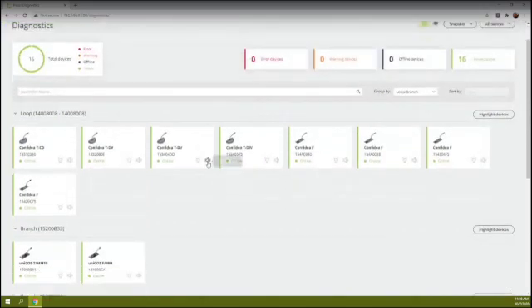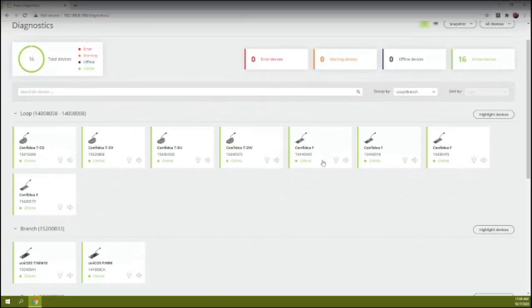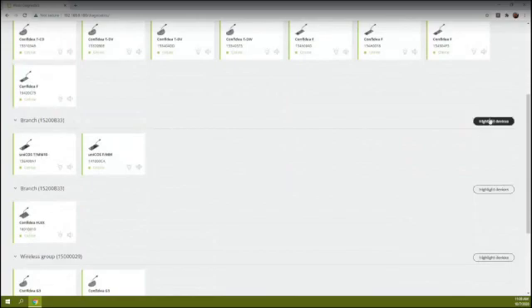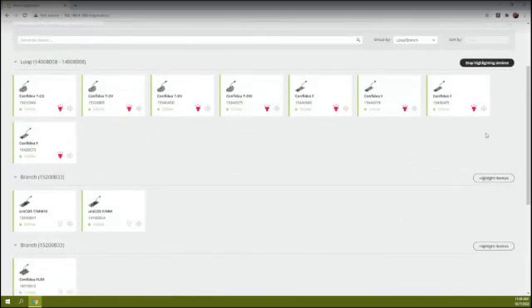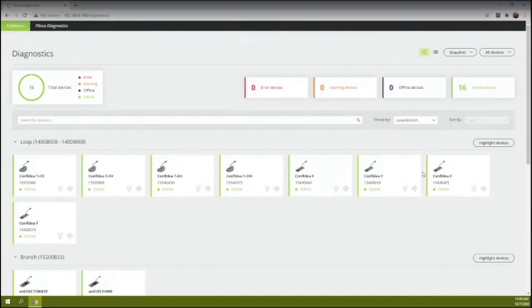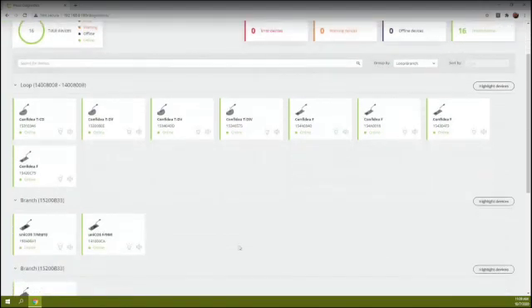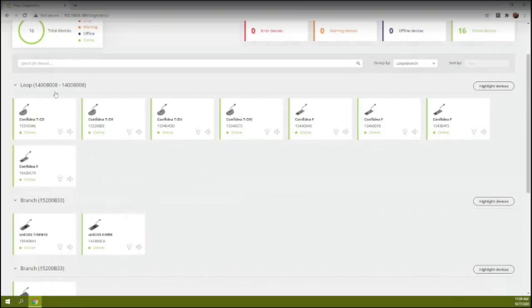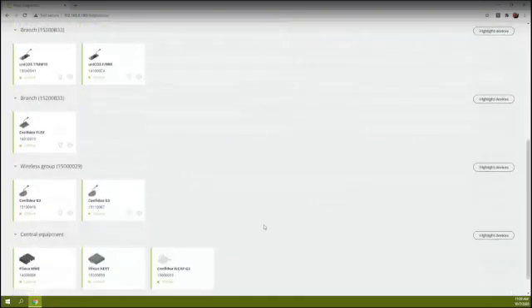There's more on this diagnostics page. I can do a test tone to any one device or all devices. I can highlight the entire branch if I want to know exactly where it starts and stops. This is a very handy tool, and I actually use this every single time I am out in the field pulling cables — because you want to make sure that if the client has demanded redundancy, the system is finished off in a complete loop.